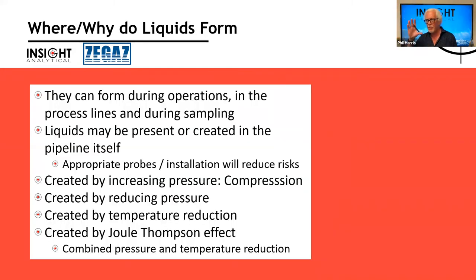So we want to think about why it is that we do hit dew points. Liquids form in our system during operation of the plant, during how we're doing compression. They'll happen in process lines, or the liquids can drop out in our system during our actual sampling process. And so if we want to try to address that, first they might be present right there in the pipeline itself. And so we have to use appropriate probes and make sure our installations are done well.